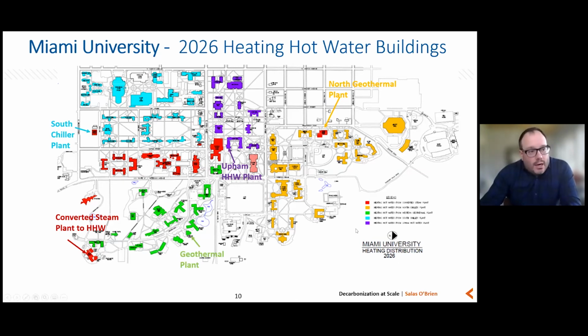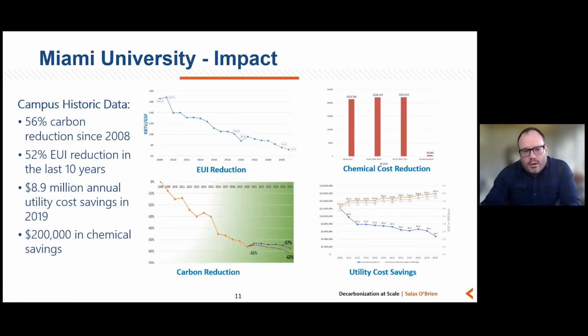This is a really interesting project in that we have very good measured information around how this transition has improved the energy efficiency of the campus, the carbon intensity, and really the cost savings that have been derived from this strategy. So again, it's a steam system being transitioned to a low temperature hot water system. You can see here a 56% carbon reduction, a very similar change in their energy use intensity, and generating about $9 million of annual utility cost savings and $200,000 of chemical treatment savings on an annualized basis.